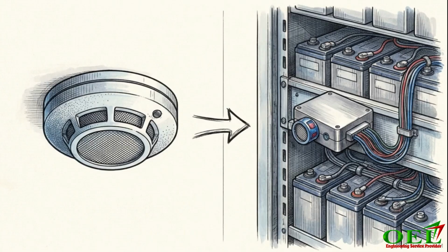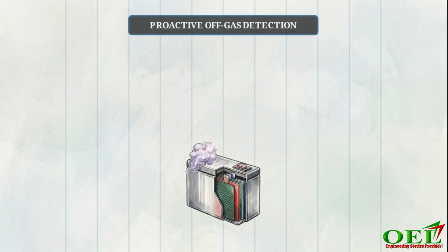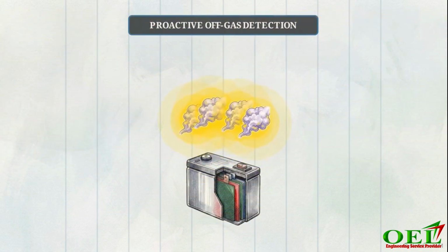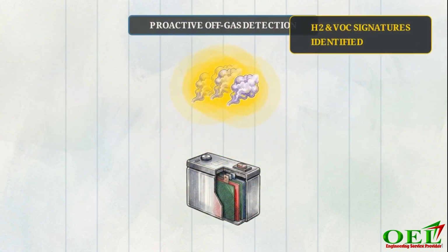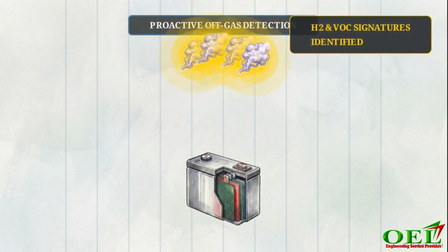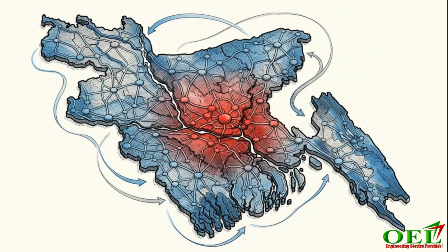These specific codes mandate a total shift in how we approach safety. Instead of reacting to a fire, the engineering requirement is now focused entirely on detecting the specific off-gases produced right before a battery fails. Constructing Bangladesh's modern grid without meeting these international benchmarks leaves the entire network exposed to guaranteed failure.